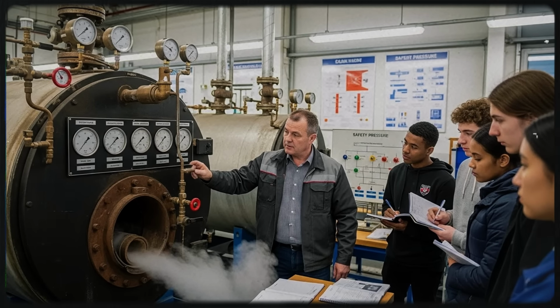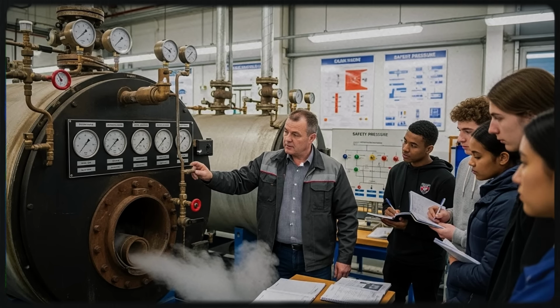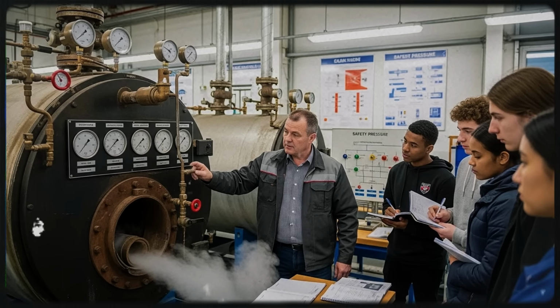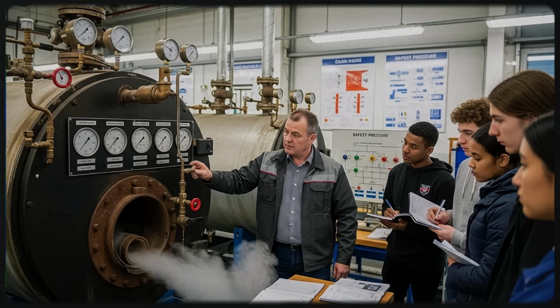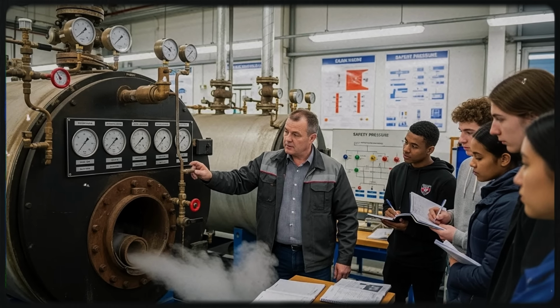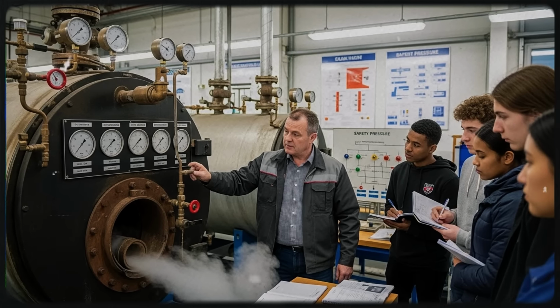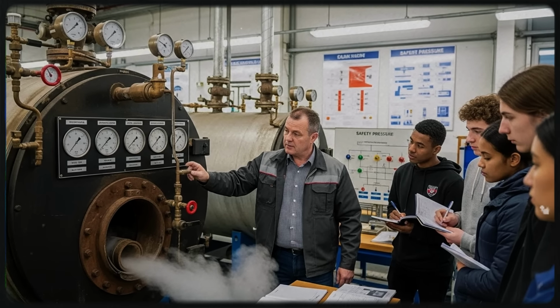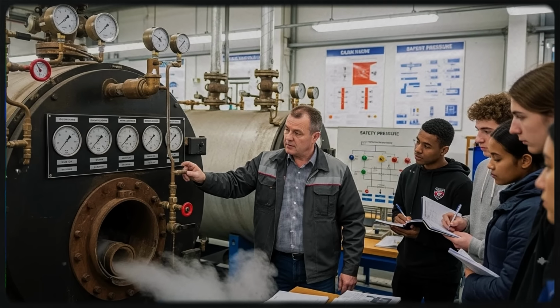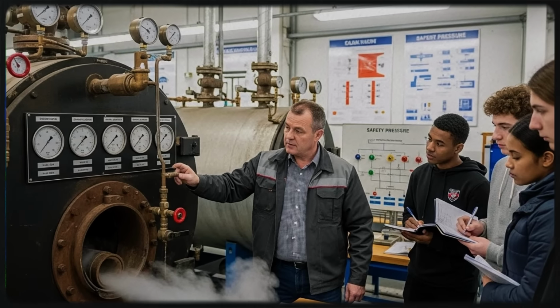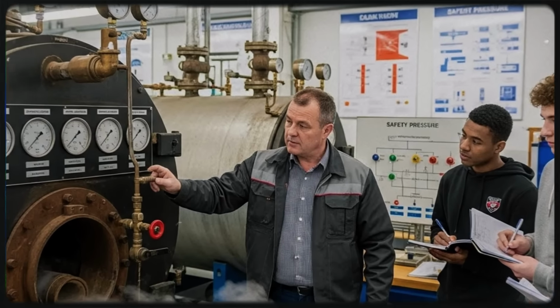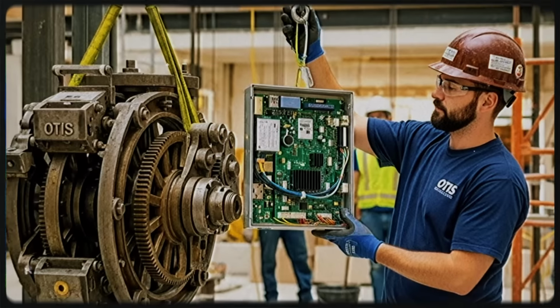Implementation, butterfly valve or guillotine valve in the steam duct between the boiler and cylinder. The engineer controlled the valve via a ratchet lever. Each increment of the lever opened the valve slightly more. A return spring ensured that if the lever was released, the valve would close automatically. The leverage system was designed to provide fine control in low opening positions where precision was most important and faster movement in high opening positions.